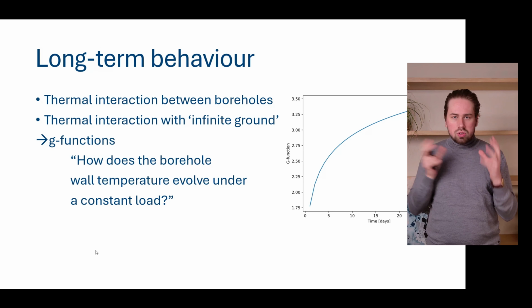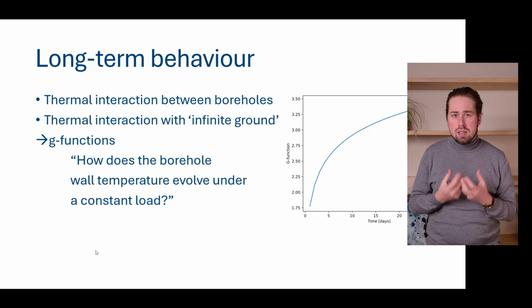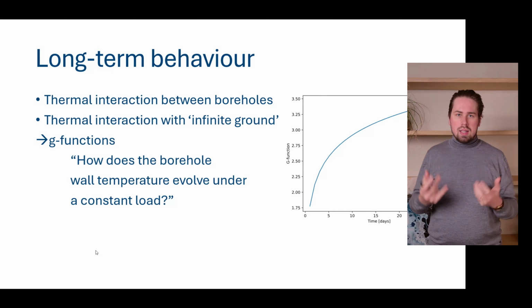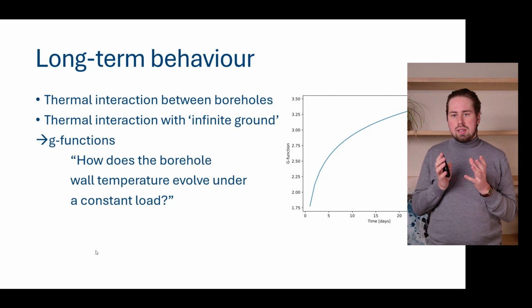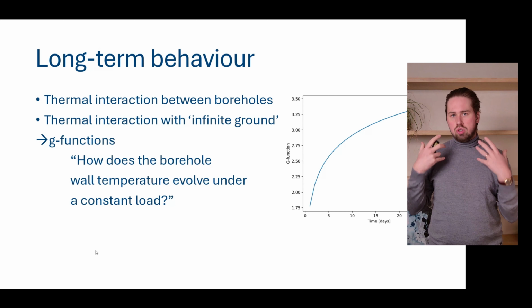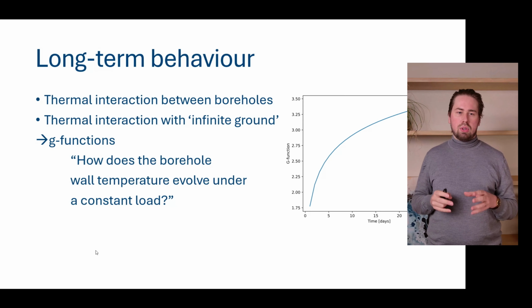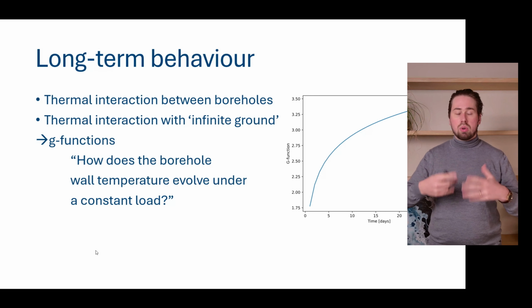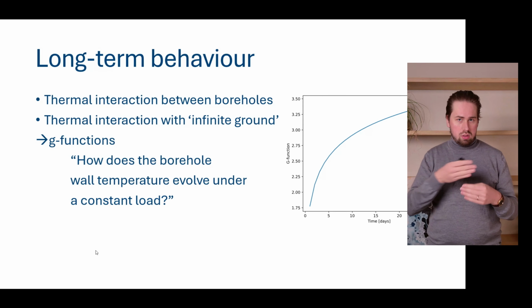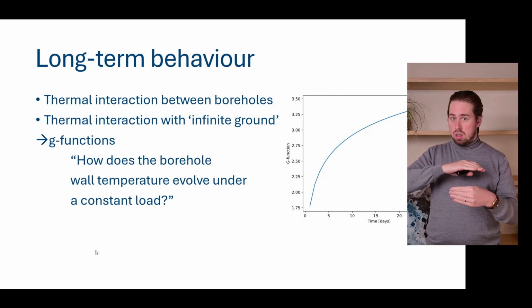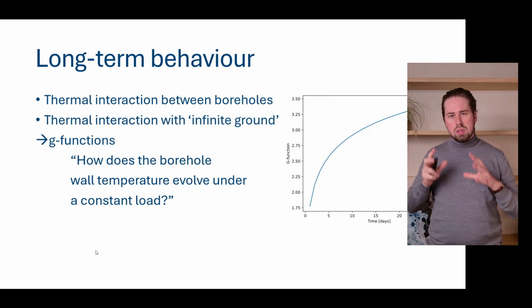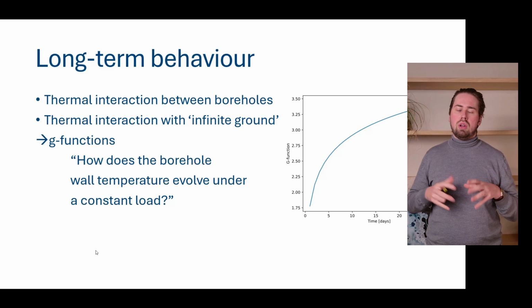In order to visualize and understand this, Eskilsson, in his PhD dissertation in 1987, conceptualized this as G-functions, which are ground response functions. You can think about these functions as an answer to the question: how does our borehole wall temperature, so the temperature at the interface between our bore field and our ground, evolve under a constant load?